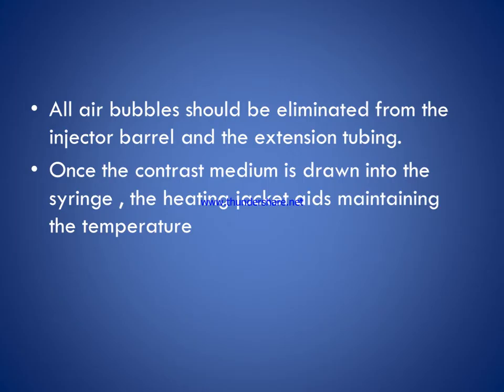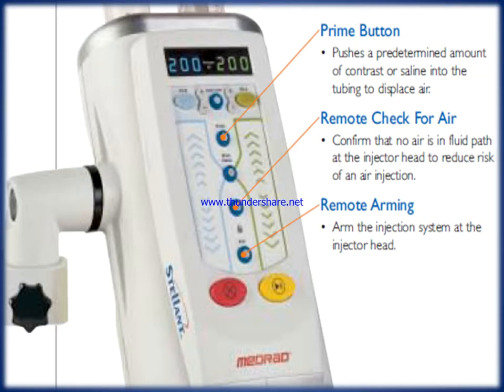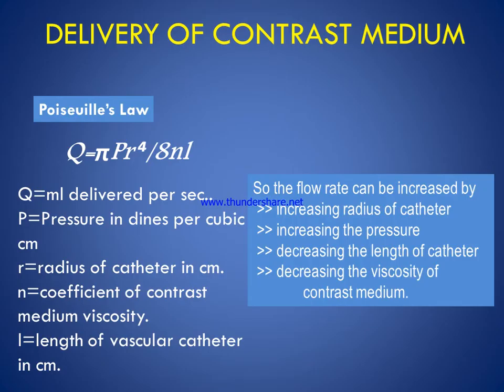Here we show the images of the control panel of the pressure injector, illustrating the use of the prime button, remote check for air, and remote arming.